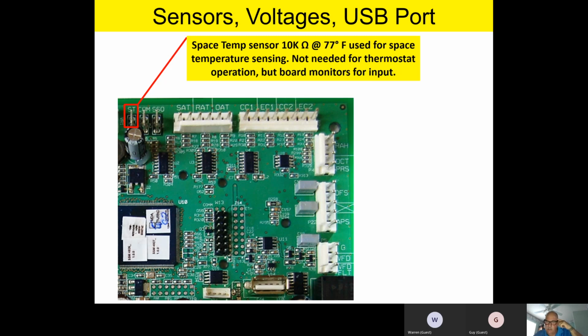No, it's just that on some versions of some boards, if they don't see the space temperature sensor, even though they're working on a thermostat, it's still going to alert the technician that it can't see space temp. So if you want to get rid of that little light, even though you're on a thermostat, you can take just a standard little Honeywell space temperature sensor, run two thermostat wires from it, and they're non-polarity sensitive, so it doesn't matter which one hooks where. You put the space temperature sensor somewhere in the space or in the return air duct, and hook it up between ST and common right next to it.